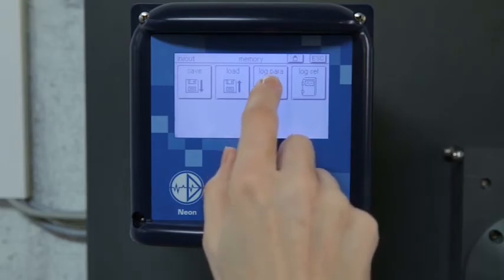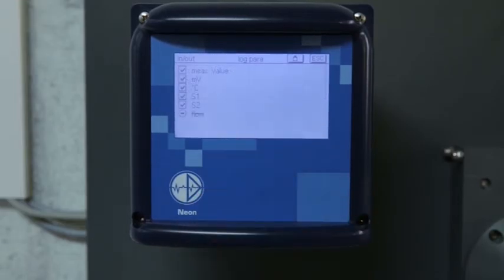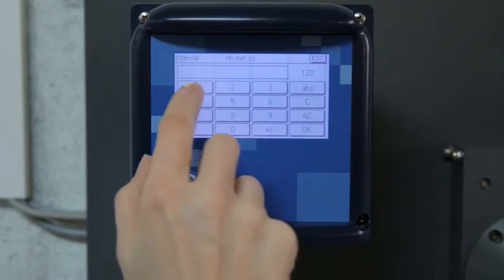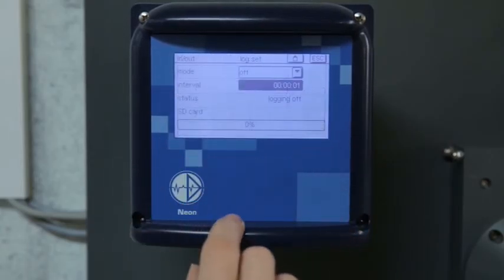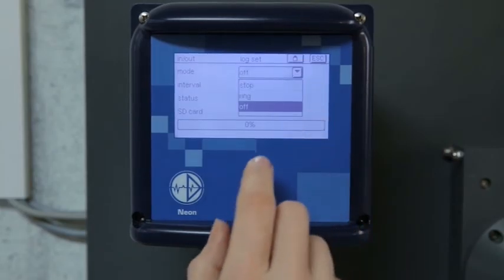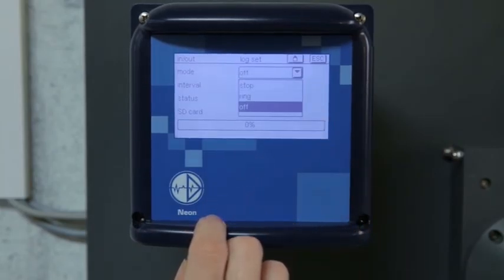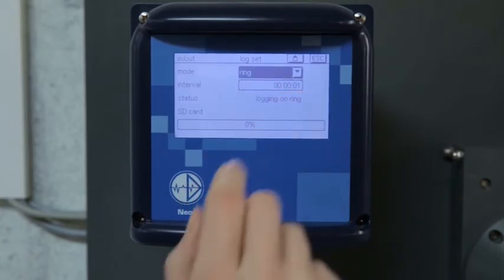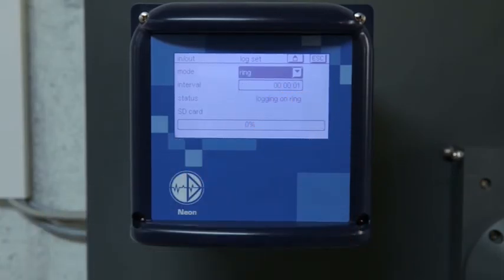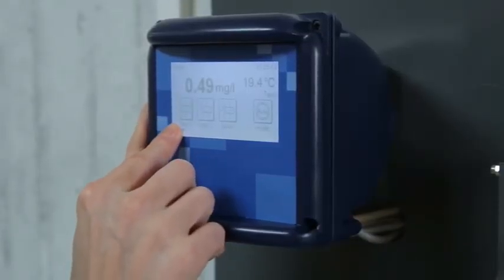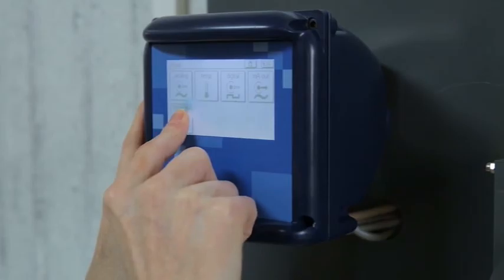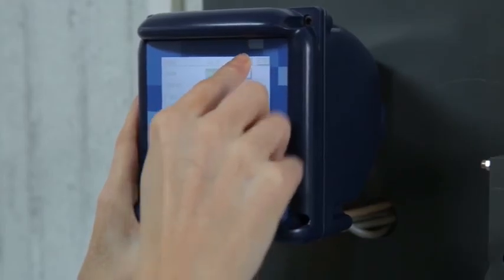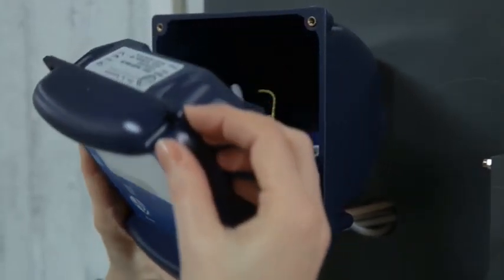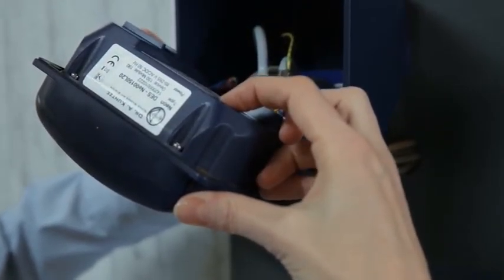The SD card function can be used as data logger. You can select the parameters to be logged. The logging interval can be selected freely. If the memory card is full, logging will either be stopped or older data overwritten depending on your specific settings. Storage space is indicated by an analog bar. To remove the SD card, first switch off the logger and take the instrument out of the housing. The SD card is in the rear in the upper right-hand corner. Push to eject.